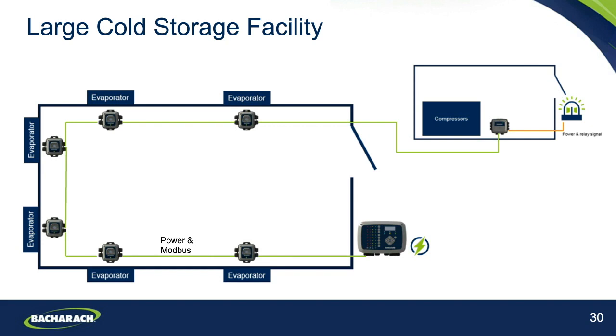We do need to look at the airflow within the room and also where a leak is most likely to arise from. But it's really a case of taking those rules and applying them to a specific application. Because of the different layouts we can have here, there's typically not one hard and fast rule that you could state that in any ammonia application, this is where you put your placement of detectors. It really can be better to look at it on the layout of the room, where people are going to be, and as I say, it may be that you want to place the toxic level detectors and potentially the higher range flammability level detectors in different places pending that specific application or layout.